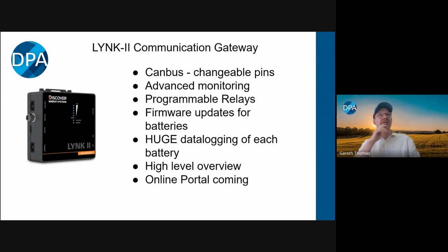It also allows a much higher level of monitoring than you'll see with, as far as I can tell, any other lithium battery product on the market. Nearly all other batteries will only give you the battery voltage, the current of the entire stack, the maximum and minimum cell voltage of the entire stack, and the state of health. Whereas with the LYNK II, you can see each individual battery - its state of charge, its voltage, the current in and out, its state of health, its serial number, the maximum and minimum cell voltages - and you can download the history for each individual battery as well. I'll go through this and show you all that.